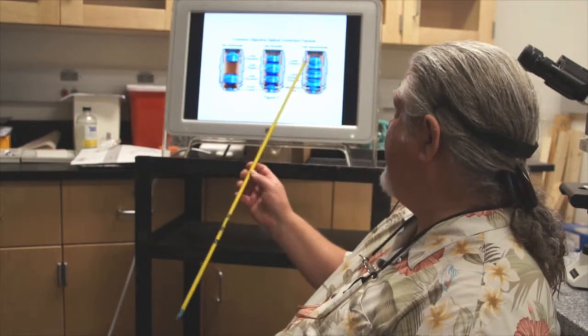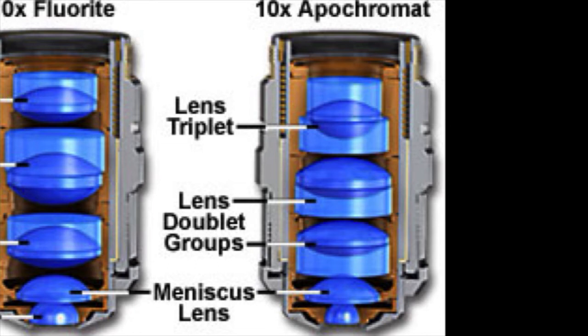Manufacturers have developed objectives called plan apochromats. It's a plan objective, which means it's flat from edge to edge, and it is an apochromat, so it's corrected for chromatic aberration. All your colors are magnified to the exact same plane, so you get sharp, crisp, flat images which are beautiful for fluorescence microscopy. Here you see an apochromat objective, but we're using plan apochromats, which are corrected not only for chromatic aberration but for flatness of field as well.